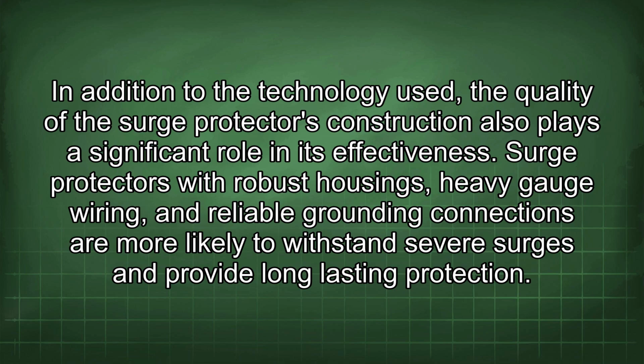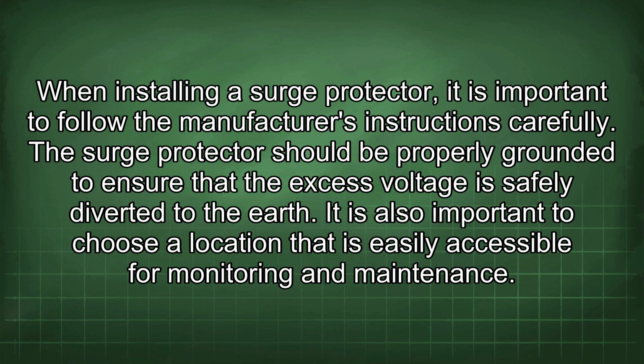Surge protectors with robust housings, heavy gauge wiring, and reliable grounding connections are more likely to withstand severe surges and provide long-lasting protection. When installing a surge protector, it is important to follow the manufacturer's instructions carefully. The surge protector should be properly grounded to ensure that the excess voltage is safely diverted to the earth. It is also important to choose a location that is easily accessible for monitoring and maintenance.